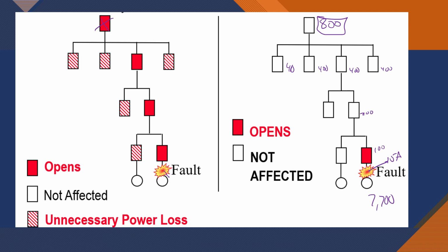So we cannot assume selective coordination is achieved if the upstream overcurrent protection device has larger ampere ratings. One of the other things here is in 2023, I think they've addressed this a little better than they did in the 2020 code, because now it also affects other feeders and branch circuits. So if you have any area that needs to be selectively coordinated, the whole place needs to be selectively coordinated. I don't have the code reference on that in front of me, but if you have the 2023 book, let's look into that, because it only makes sense that we're going to be selectively coordinating everything, not just those things that are in line with a particular area.